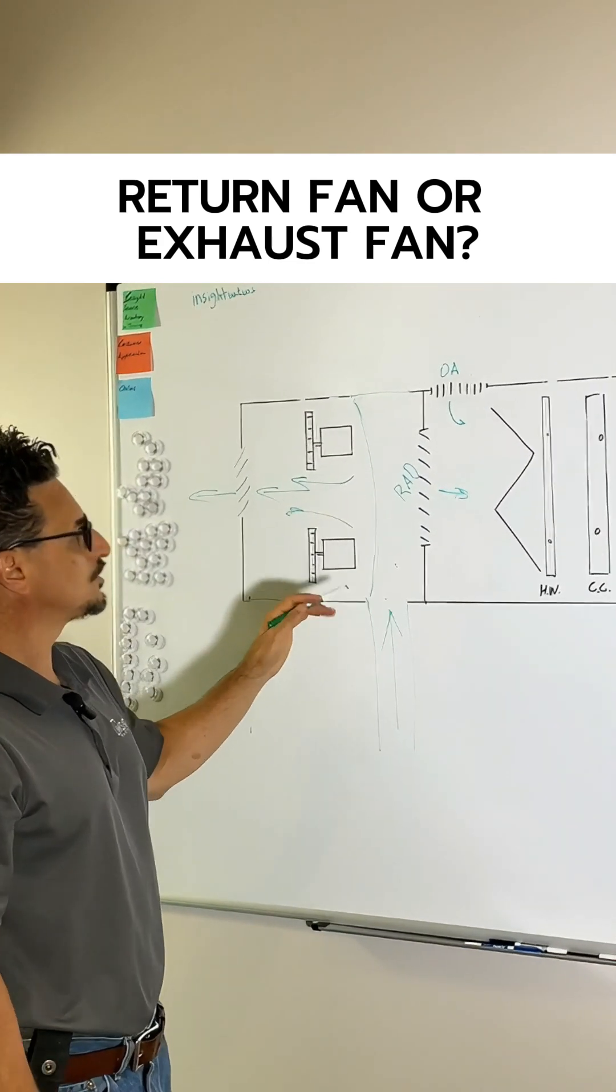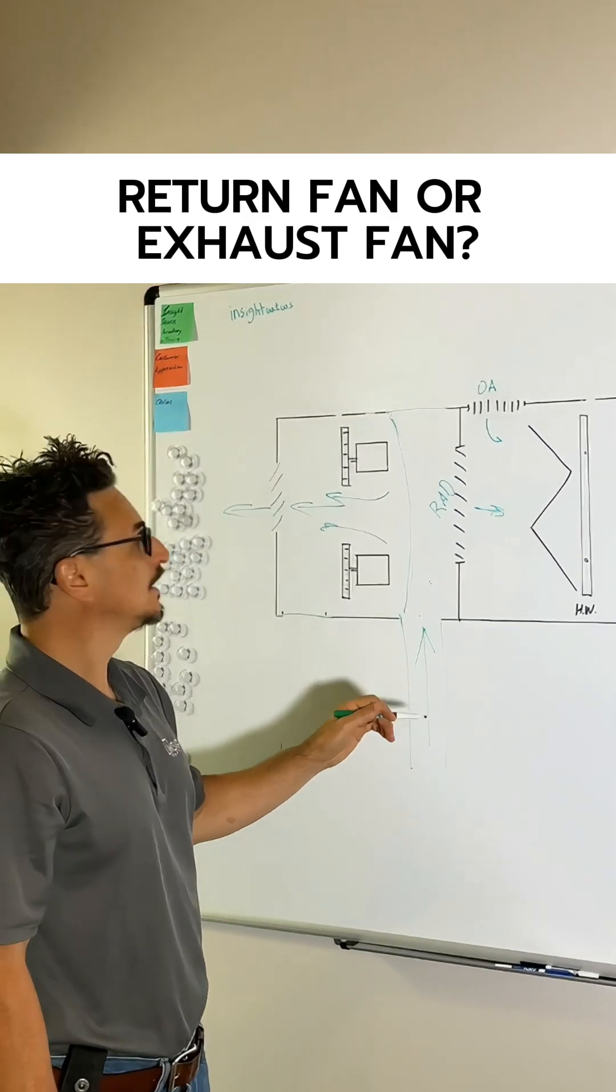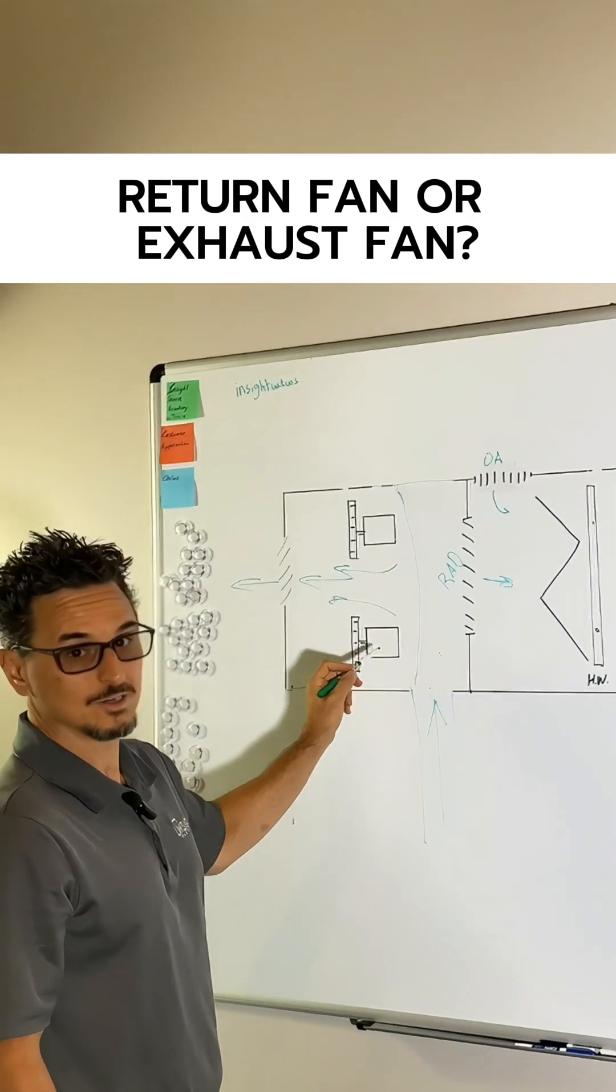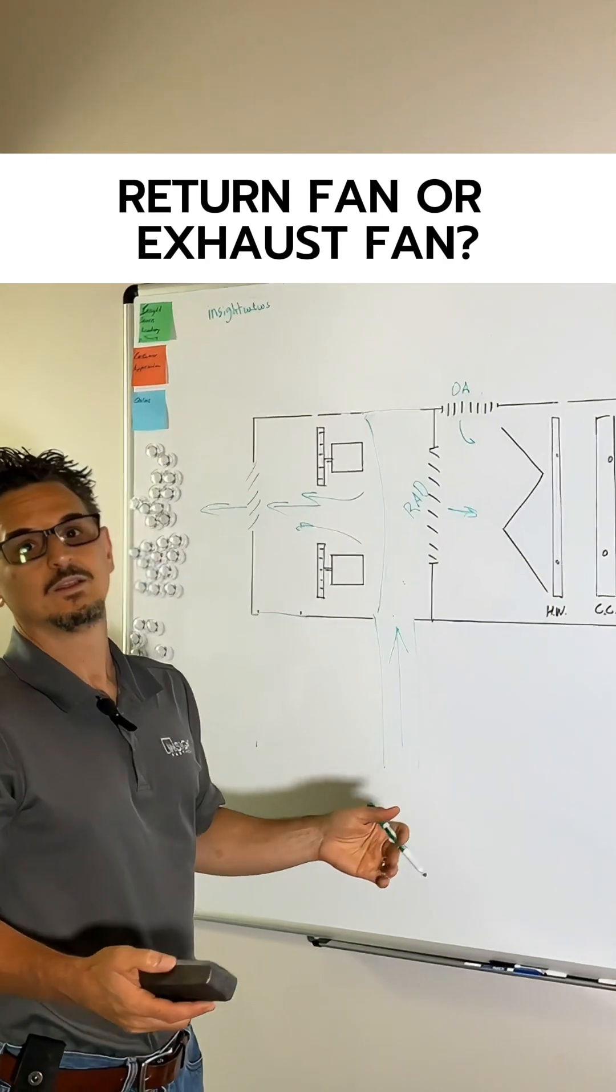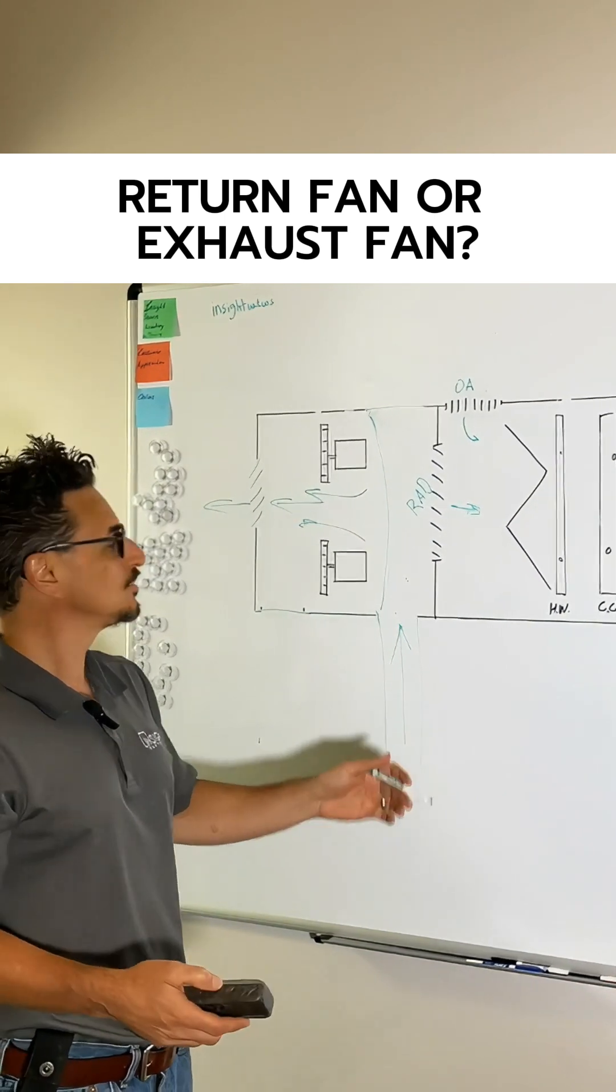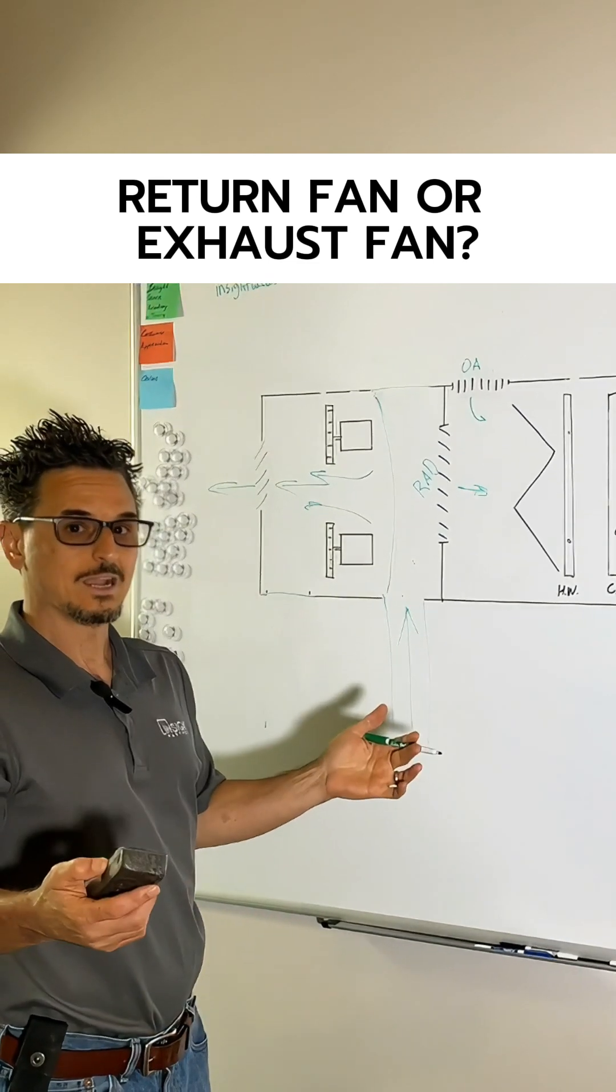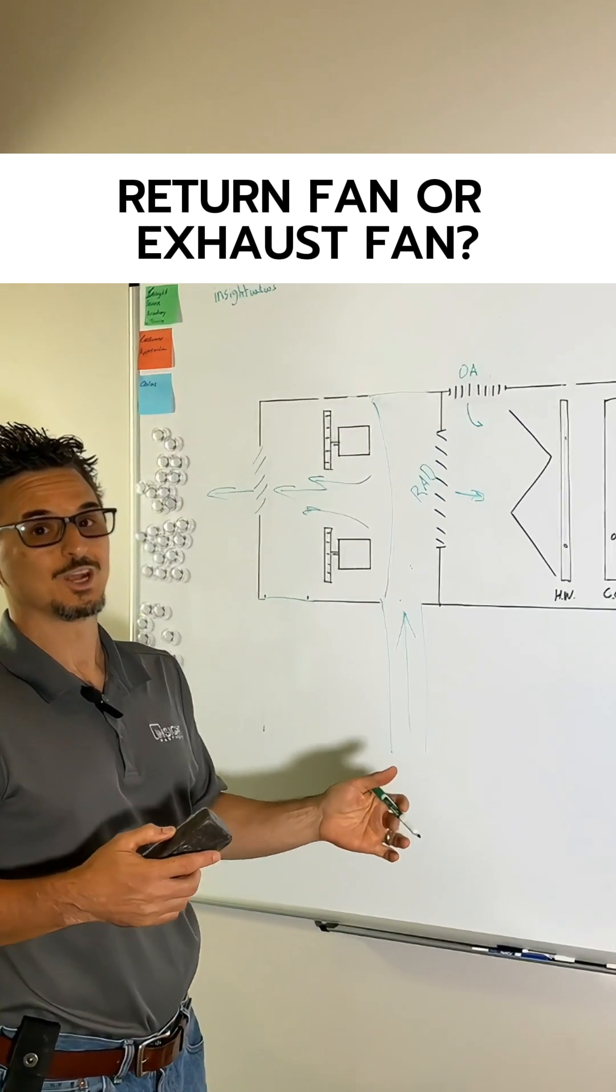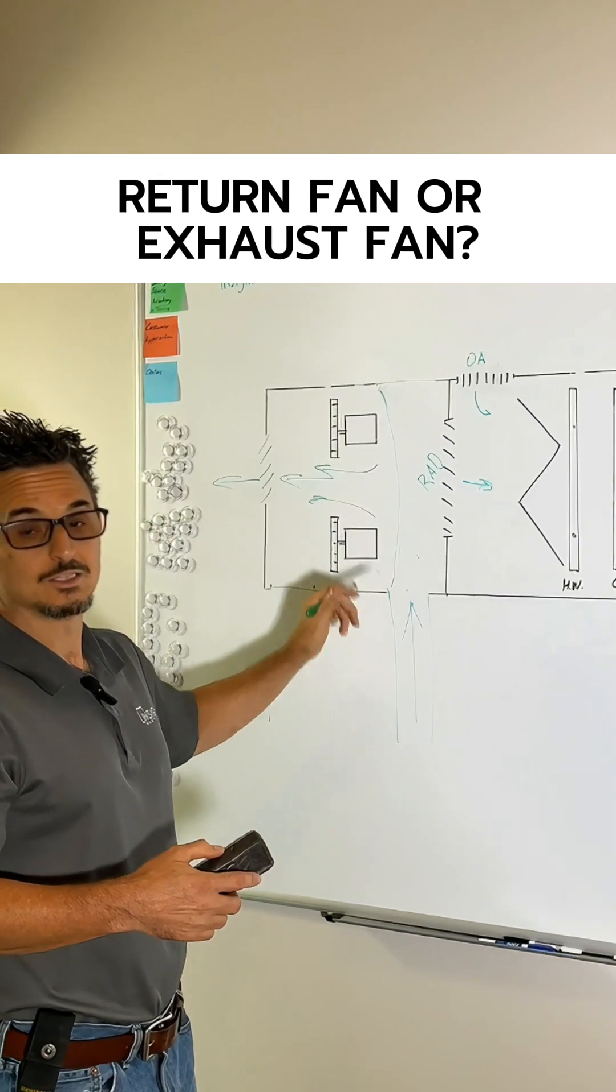So one of the challenges or one of the things to be concerned with is if you're going to do 100% economizing, make sure that these fans are designed for 100%. A lot of times when we're selecting package DX equipment, we might be selecting a 5,000 CFM unit with 20% outside air, right, and usually the exhaust fans are only sized to handle that 20% design outside air. So if you want 100% economizer scenario, make sure that in that scenario these fans would be sized for 5,000 CFM.